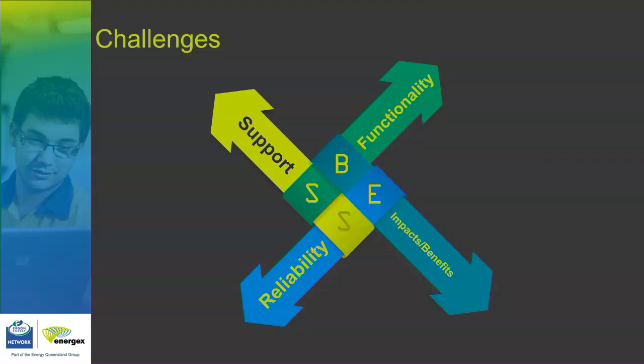Some of the impacts we've had, we might have pushed some volts a little bit high on a few feeders when the system was meant to discharge, but was charging when it should have been doing the opposite, and we've pushed the volts either too high or too low. Sometimes all that takes is an incorrect setting in a controller. Really simple mistake, or a sensor goes corrupt. You lose comms to it. We've had it happen.